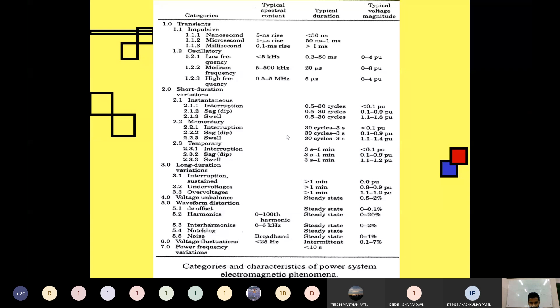So now, same way, the last category, the third category in oscillatory transient, high frequency. Again, frequency is more than low frequency and medium frequency, between 0.5 to 5 megahertz. So again, time is reduced as compared to the previous two categories. It is between 20 microsecond to 5 microsecond. If oscillation happens for a duration between 20 microsecond to 5 microsecond, the frequency of this oscillation is between 0.5 to 5 megahertz, and voltage variation is between 0 to 4 per unit, in terms of voltage 0 to 400 volt, if 100 is the rated voltage, then we can say that it is a high frequency oscillatory transient. Clear, all of you?